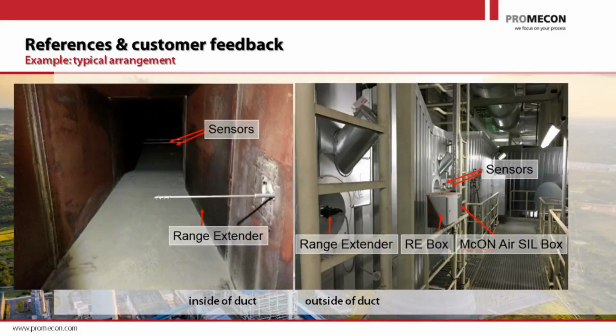So what we have done is we went into the shallow section of this duct, and we installed 2 sensors. And then before the sensors, we also installed the range extender. And from the outside, you can see the range extender as well, the box, and the 2 sensors. And we have been using the system for many years. And the system, again, never been recalibrated, never been maintained in such a way. The only maintenance that they have to do, the system is a so-called SIL2 rated system, so it's a safety integrity level 2 system that is mandatory in Germany.